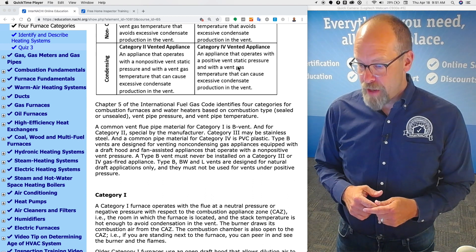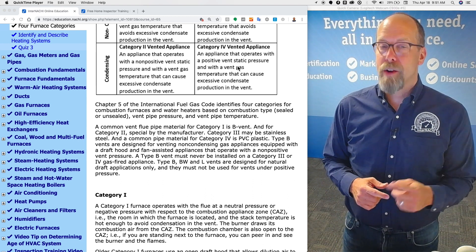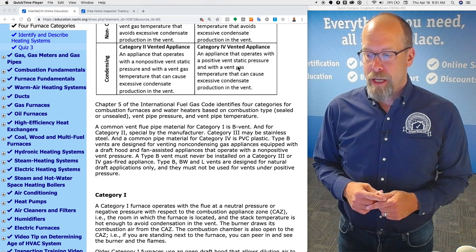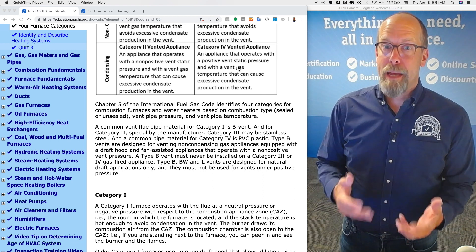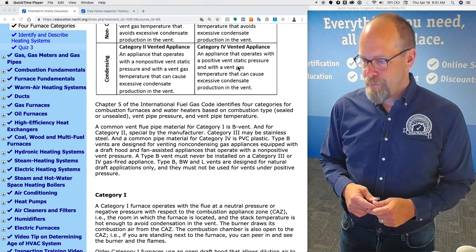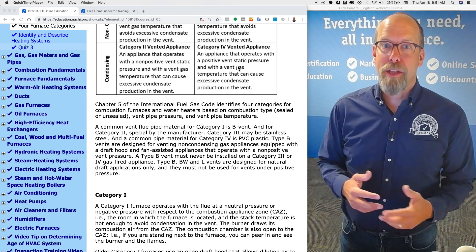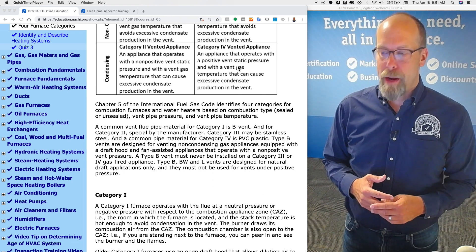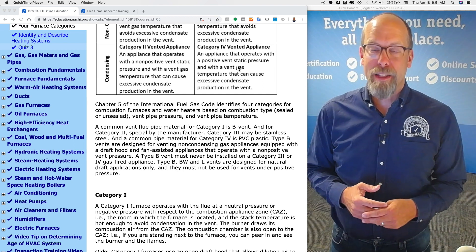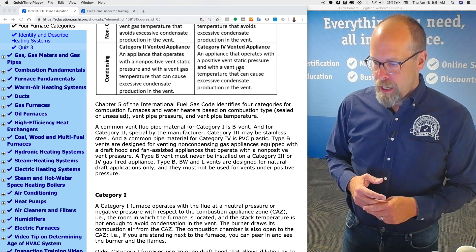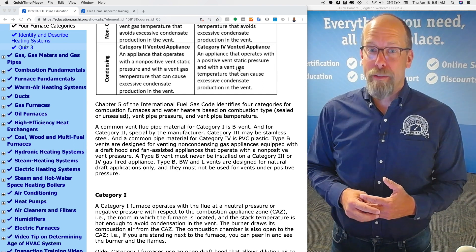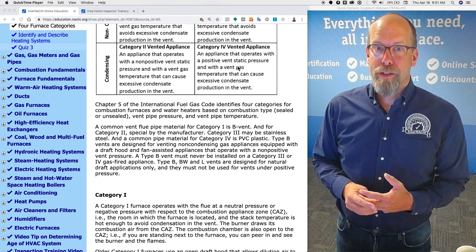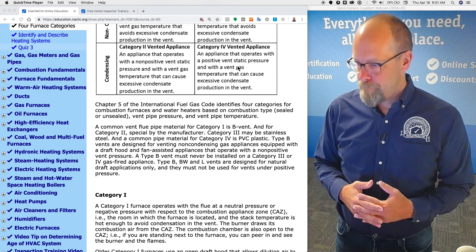A common vent flue pipe material for category one is B vent or type B. For category two, it's a specialized kind of thing by the manufacturer. Category three may be stainless steel, and a common pipe material for category four is PVC or CPVC.